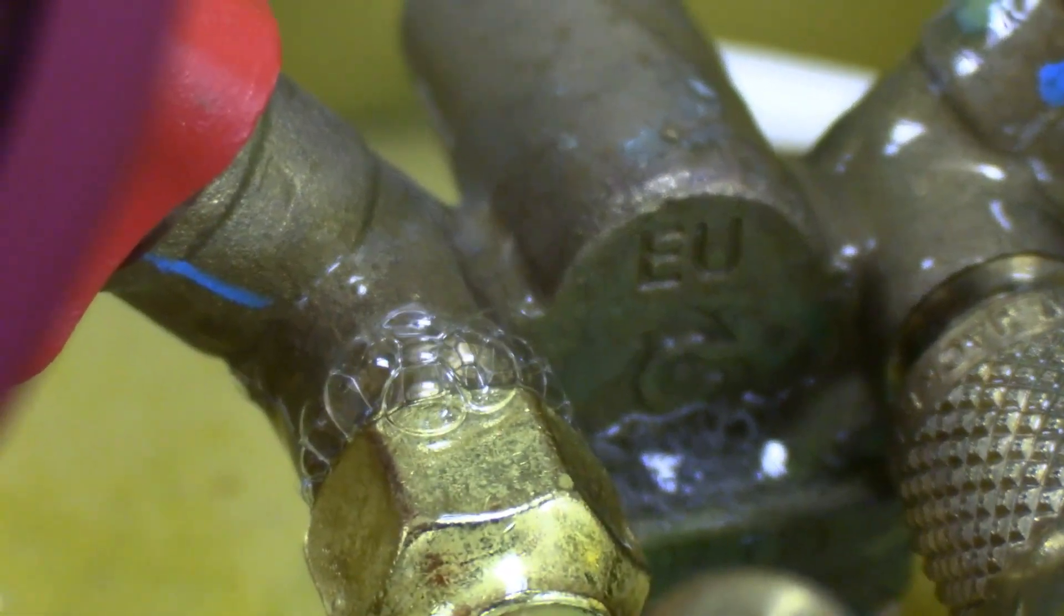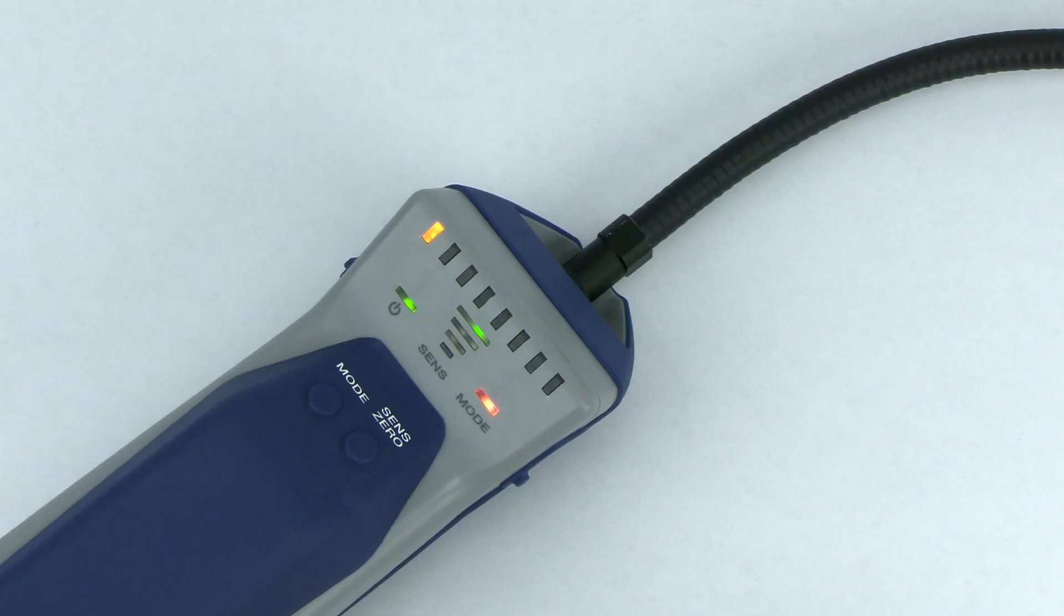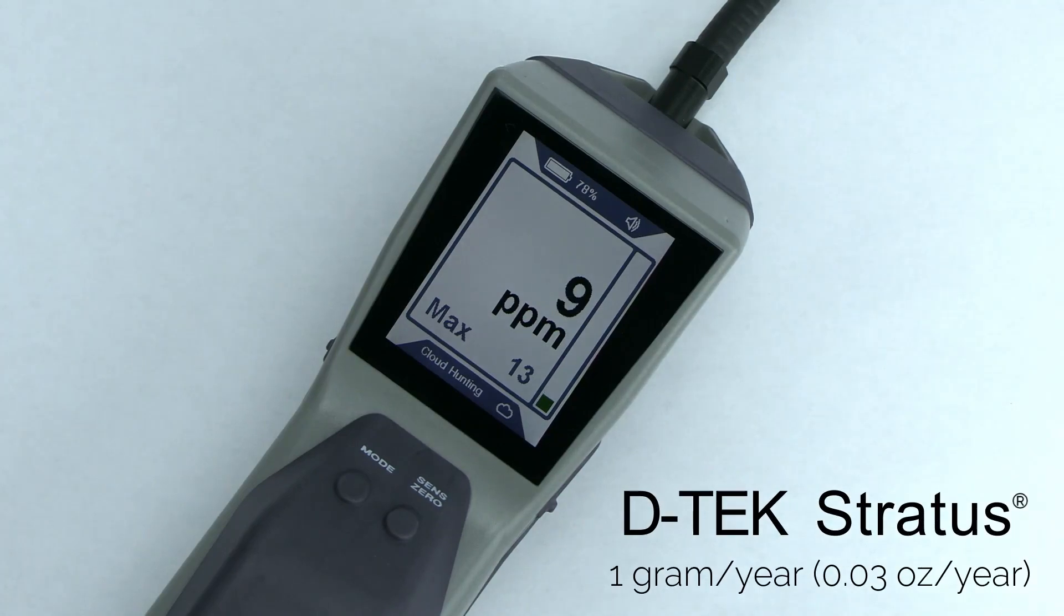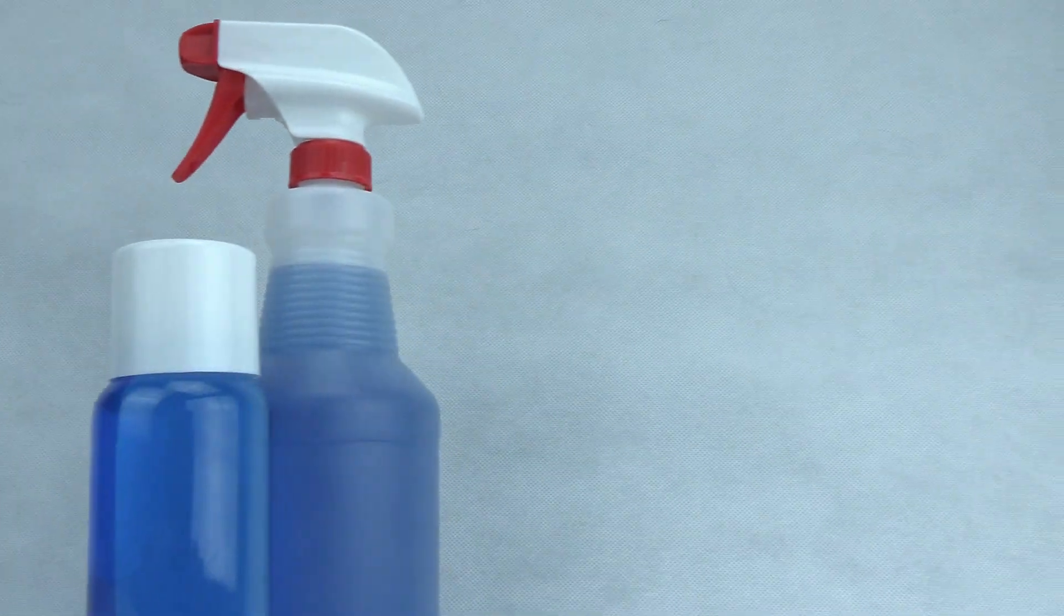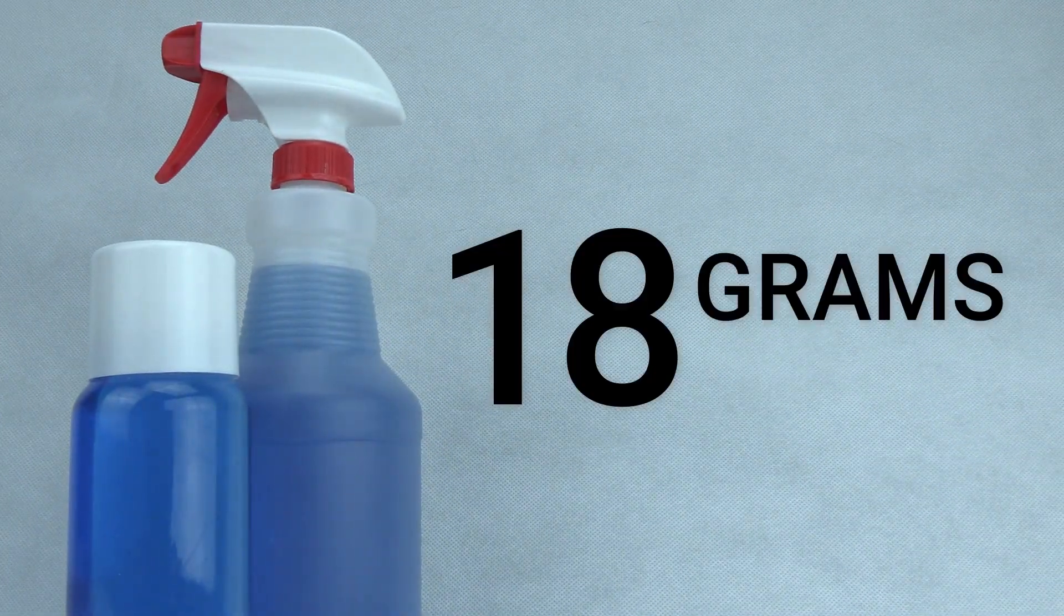Inficon's lineup of electronic leak detectors are engineered to repeatedly detect leaks as small as one gram per year. Soap bubbles are only sensitive down to about 18 grams per year, which is over 10 times less sensitive than some electronic detectors.